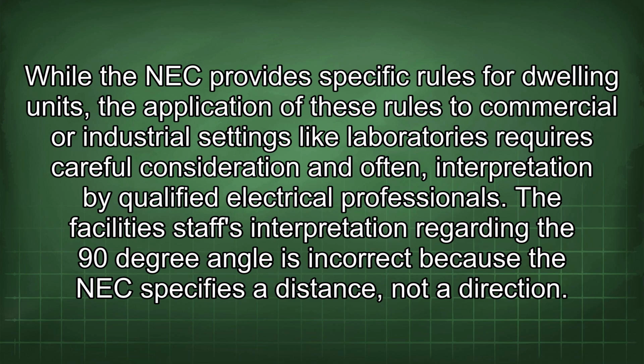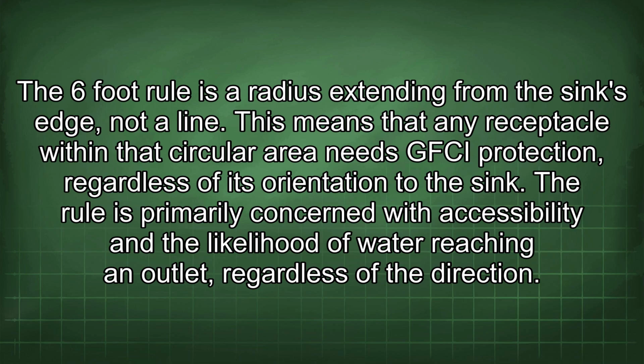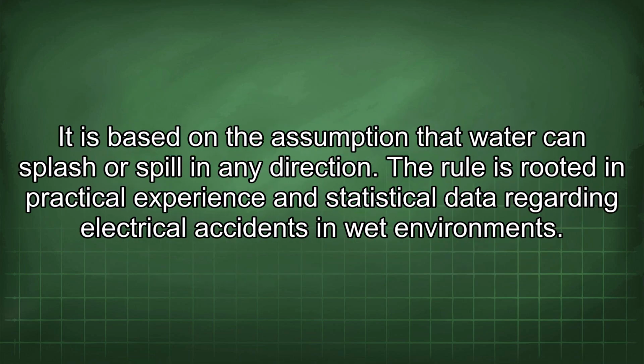The facility staff's interpretation regarding the 90-degree angle is incorrect because the NEC specifies a distance, not a direction. The 6-foot rule is a radius extending from the sink's edge, not a line. This means that any receptacle within that circular area needs GFCI protection, regardless of its orientation to the sink. The rule is primarily concerned with accessibility and the likelihood of water reaching an outlet, regardless of the direction. It is based on the assumption that water can splash or spill in any direction.